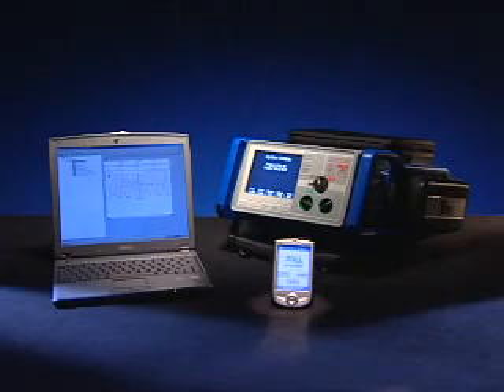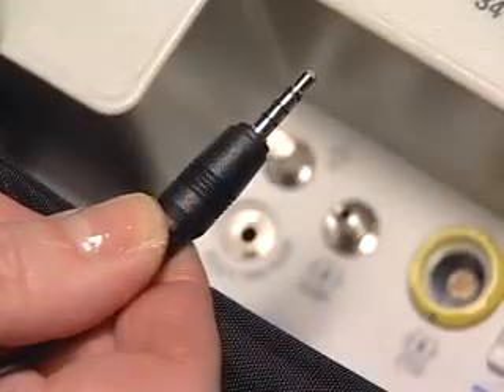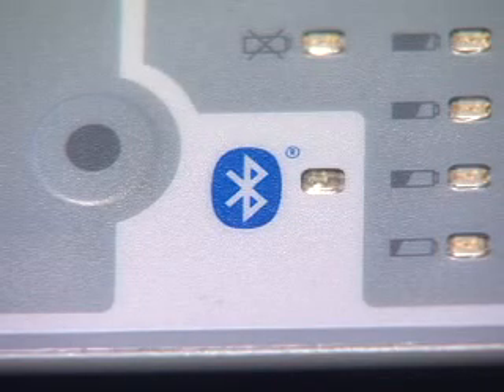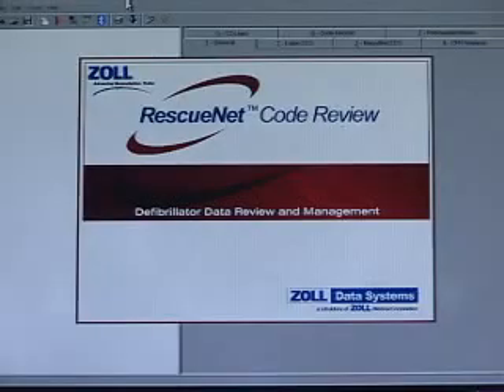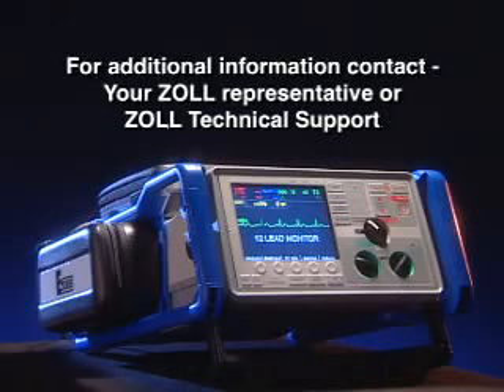ZOLL E-Series data can be uploaded to a PC or a handheld device via 2 transmission methods. Either using the RS-232 cable attached to the RS-232 port or the integrated Bluetooth wireless option. On the PC, you can use ZOLL's RescueNet Code Review as your receiving software. For additional detailed information on the operation of your E-Series, contact your ZOLL representative or ZOLL technical support.